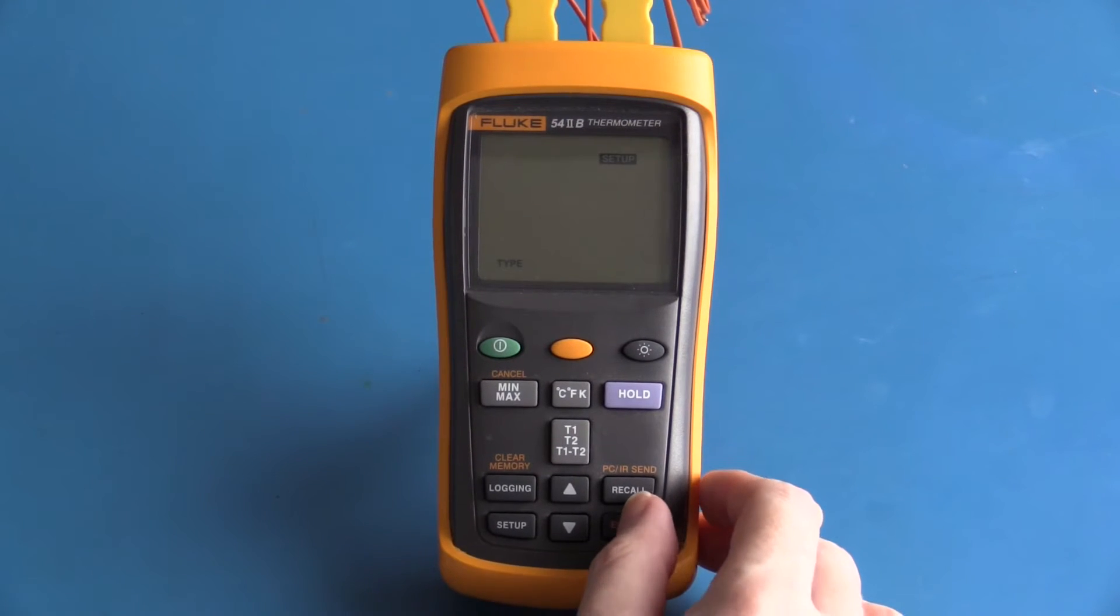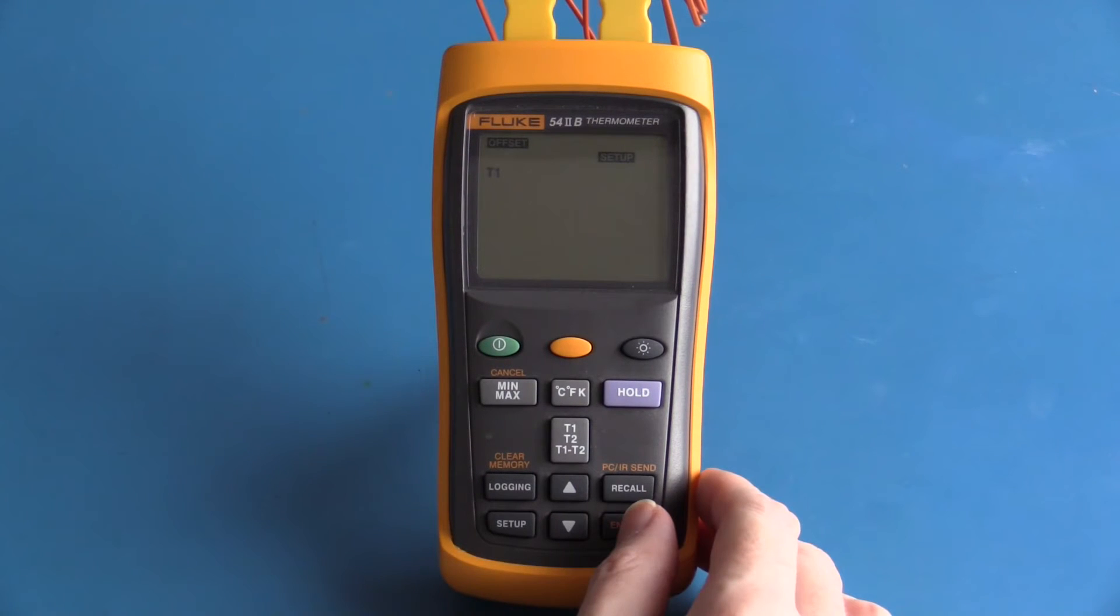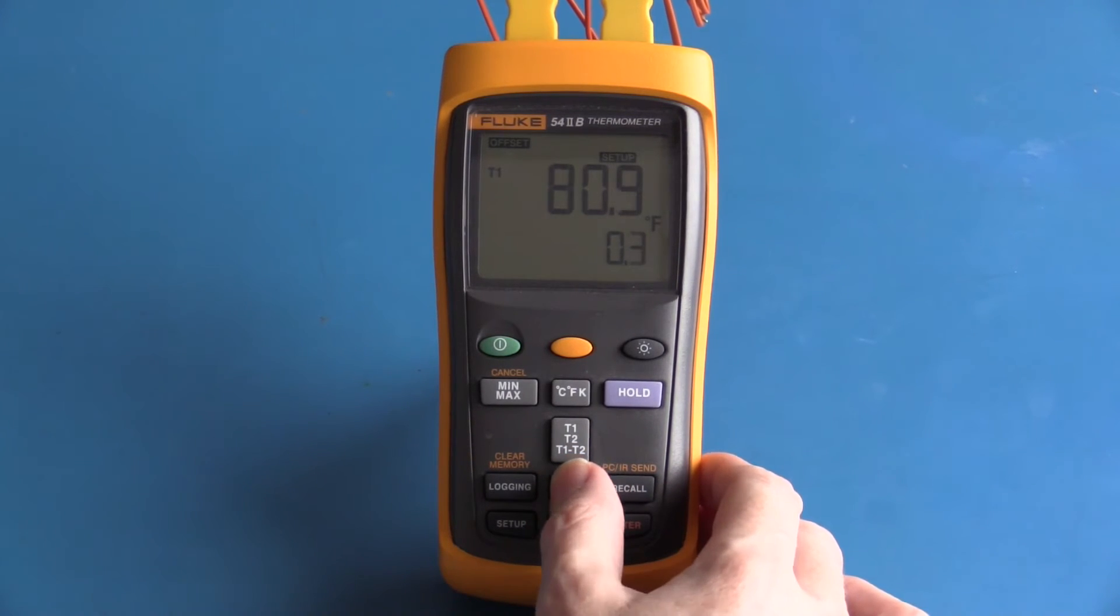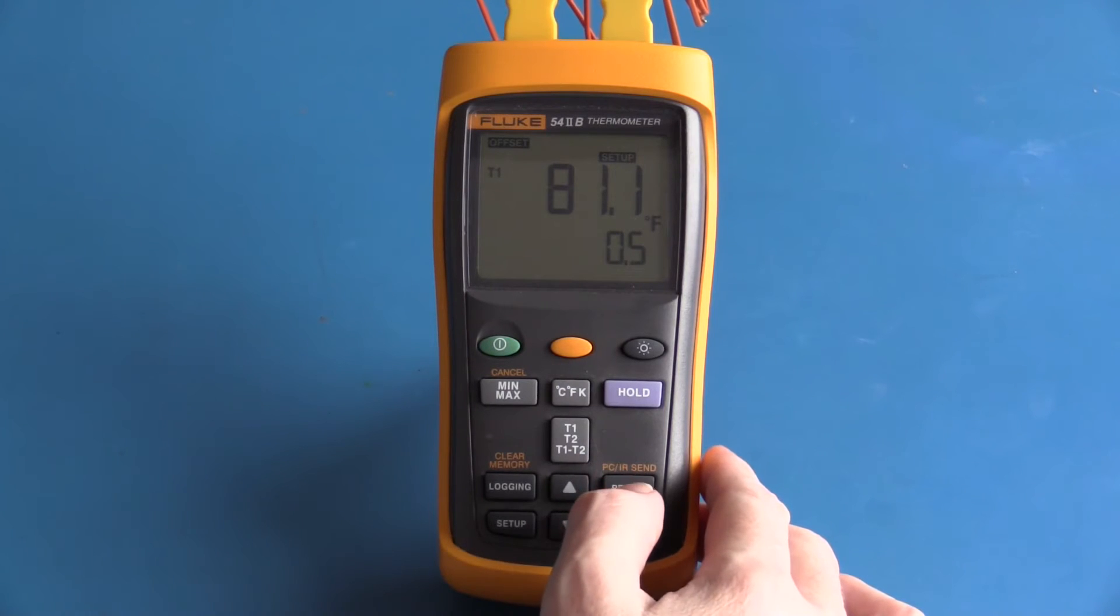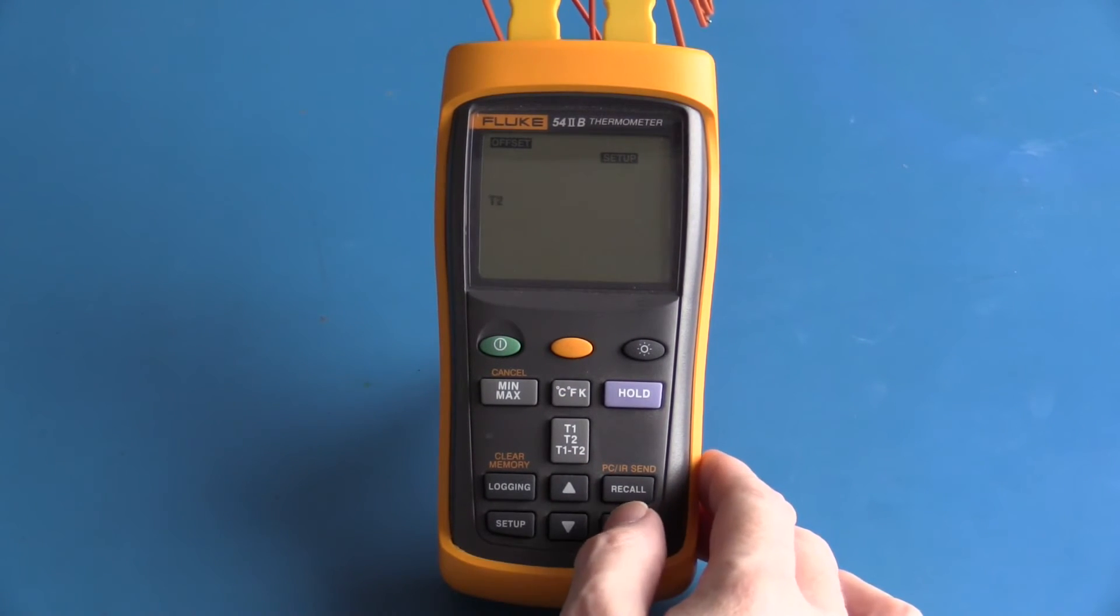The type tells the thermometer what type of thermocouple we are using. Our options are K, J, T, E, R, S, or N. I only have K type thermocouples. Each channel can have a fixed offset which is applied to the reading. So for example, if I wanted to I could set a half a degree Fahrenheit offset for T1. I don't wish to set an offset. Likewise an offset can also be set for T2.